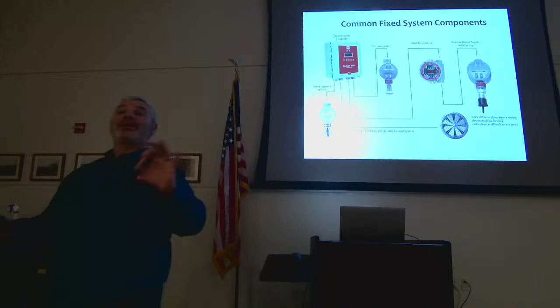You just put a transmitter in place and you walk out to this with a voltmeter and some calibration gases, and you can do everything at the point of gas detection. So John, that's great, but if I'm out in that room, there's no LED display on it. I don't know what's going on in that area. Oh, we've got a fix for that. It's called an M2A. It's got a little digital display on it. It'll do the same thing this does, but it'll tell you how much gas is there. It'll then push that signal back to the controller as well.